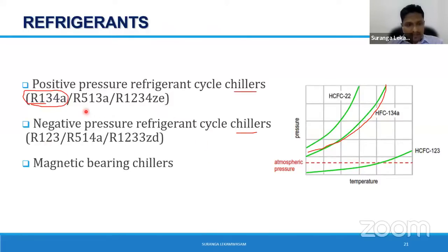Then, of course, with the global impact of refrigerants, people are now inventing what we call new generation refrigerants. Instead of R134A, which has a high potential for greenhouse effect, this gas is being replaced with new refrigerants like R513A and R1234ze. It's similar with R123, because R123 has a very high ODP value, ozone depletion potential. Therefore, by 2030, we have to eliminate this gas, right? This is a very efficient chiller. But now manufacturers have invented new generation refrigerants like R514A and R1233zd, which will give the same level of performance as R123. So this is the advancement of refrigerants.